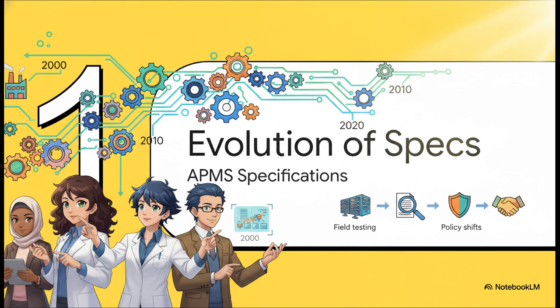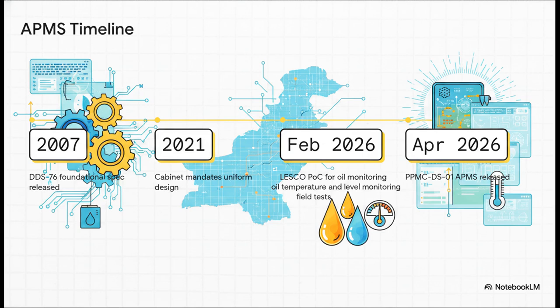Starting off with Section 1, Evolution of APMS Specifications. Let's map out the timeline, because these critical specs didn't just appear out of nowhere. They actually evolved over almost 2 decades of intense field testing and policy shifts. We start way back in 2007 with the foundational DDS-76 framework. Then, a massive shift happens in October 2021 when the federal cabinet stepped in and mandated a uniform grid design across the distribution sector. That push for standardizing things led straight to the crucial February 2026 LESCO field tests. Those tests were a real game changer, proving we could actually add new oil temperature and level monitoring safely. And all of that culminated in the comprehensive April 2026 release of the APMS standard we're breaking down today.